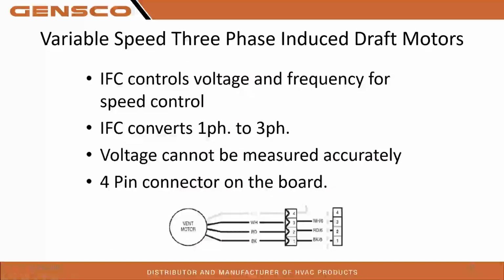All right. So let's talk about these control voltages and frequencies, right? So we have the fan control, the IFC. The main control board takes that single phase and converts it over to 3-phase. Trane has never published voltages for that inducer motor. So if you call up and say, what should it be putting out? We don't know. They've never told us accurately, low stage is this, medium is this, and high is that.